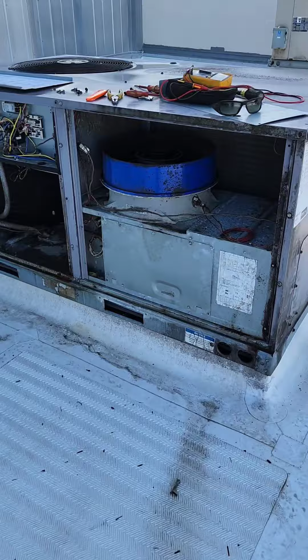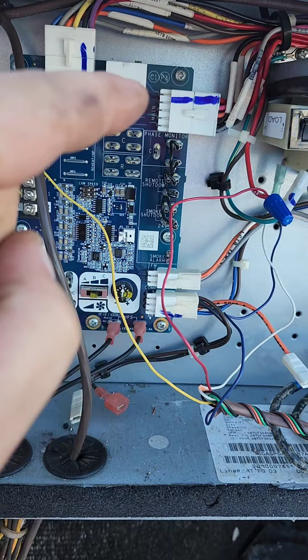So with troubleshooting, R had no voltage. There's R and C auxiliaries right there, no voltage. All those jumpers have 24 volts though. The plug on the top right with the blue has 24 volts coming in, piggybacks to that backboard. That other board has no voltage. Transformer has voltage, everything else works.